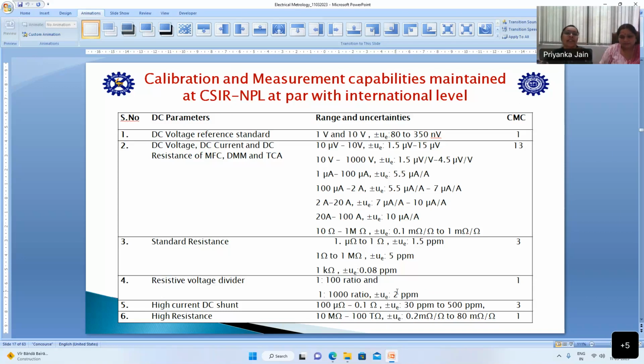Thank you. We will start with our CMCs under this particular section, LF, HF impedance. In case of any queries on the previous presentation, you can ask them at the end of the presentation. I will start with the CMCs of NPL in this division, first the DC metrology, where we have 22 CMCs. A CMC is a calibration and measurement capability of an NMI. It is displayed on the KCDB website of BIPM. That means if we have a CMC on the KCDB website, it is agreed internationally and the certificates provided on that basis will be accepted internationally. Here all the 22 CMCs have been explained.